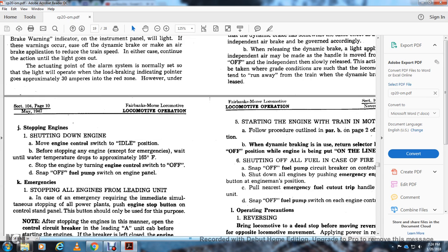Alright. Stopping the engine: shutting down the engine. Move the engine control switch to idle position before stopping the engine, except for an emergency, when the water temperature drop is approximately 165 degrees. Stop the engine by turning the engine control switch to off, and the fuel switch on the engine panel. For an emergency stop of all the engines from the leading unit, where the emergency requires immediate stopping of all the power plants, push the engine stop button on the control stand. The button should be used only for this purpose.